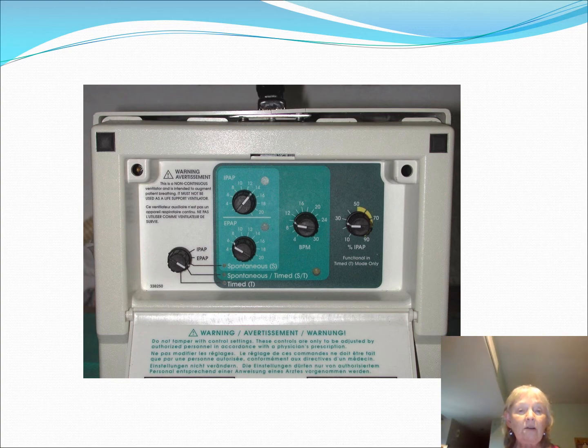And this is what the back looked like. You had spontaneous, here's your IPAP, your EPAP, and you could set a backup to it at this particular point. Over on this one, over here, there was really no backup, but this is your backup. And then we were also able to control the timing of how long we wanted the patient to be in inspiration. At that point, we really don't do that much anymore.